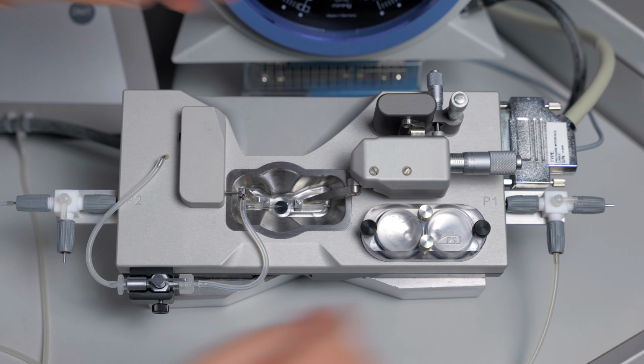We will also need to put the calibration shunt in place on the chamber. The right side will go down to the metal port coming from the P1 side. The left side will replace the tubing, leaving the P2 cannula. Disconnect the P1 cannula tubing. Disconnect the P2 cannula tubing and put the calibration shunt in place. The last thing to check are the three-way valves on either side of the chamber. You need to make sure that the valve is pointing to the open side of the three-way valve. The P2 three-way valve will be closed to the port that's pointed down. When everything is properly in place, you can proceed to the next step on the pressure calibration menu.